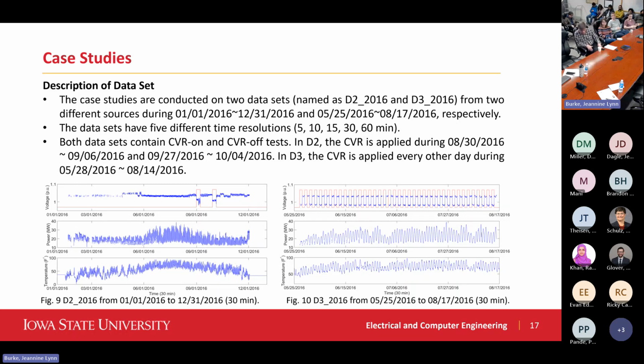In D2, CVR is applied during this time frame and not during the other time frame. So in D2 you apply CVR continuously — you didn't do on-off every day. You do that for a long time, multiple days, then you raise the voltage back, then lower it down again, and stay at the low voltage for multiple days.